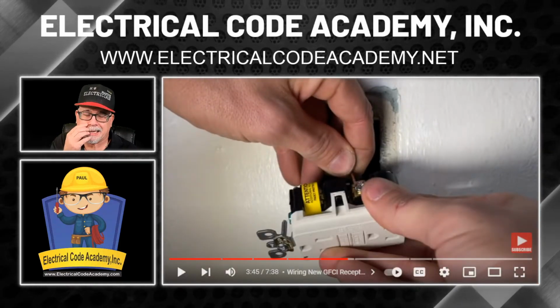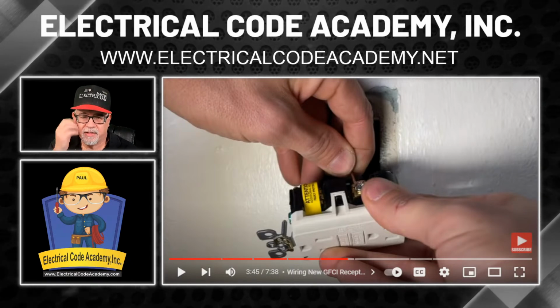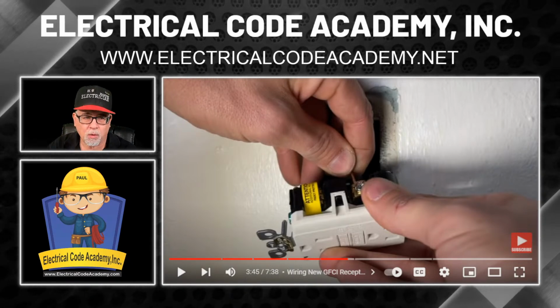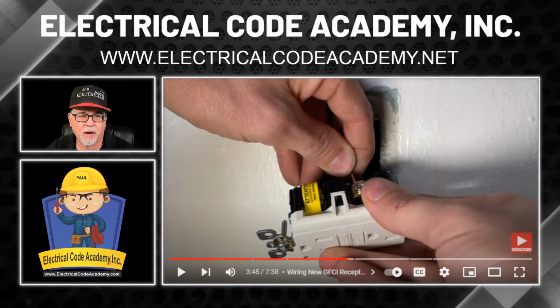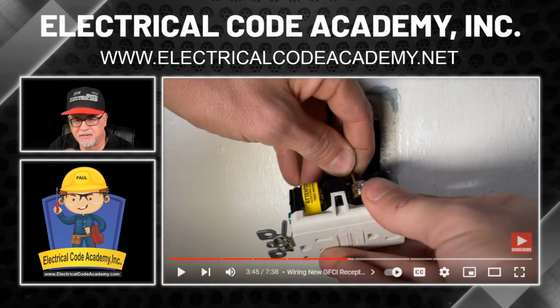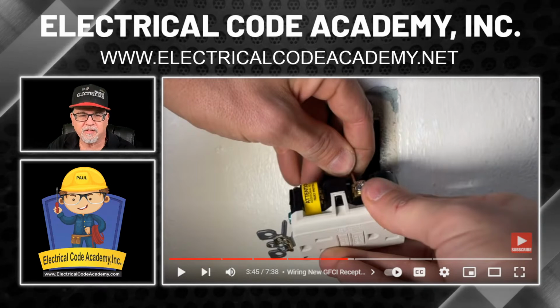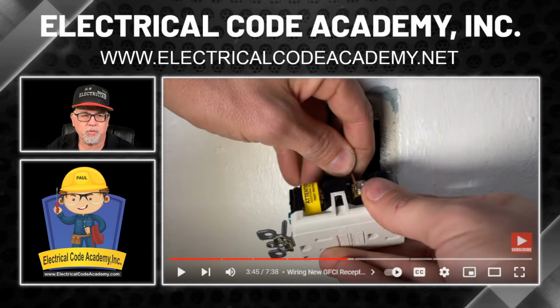Now, whether you like it or not, some of these devices will have this. Some of them will have a back wire, because 15 amp typically have a back wire. You won't get back wire on 20 amp. I see this looks like a 15 amp GFCI because it doesn't have any T slot on the neutral side.